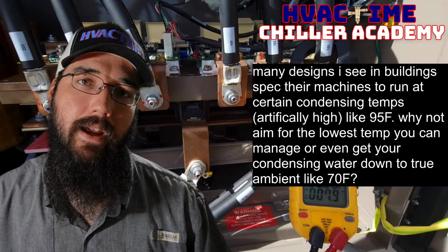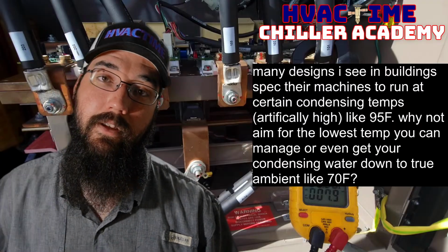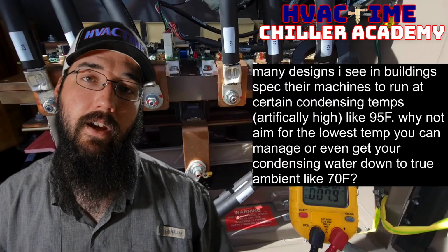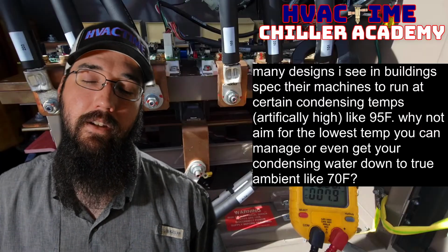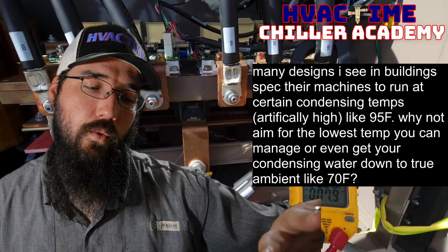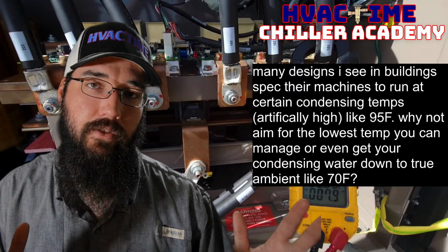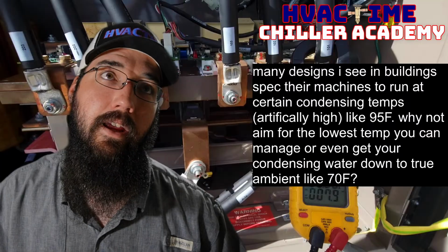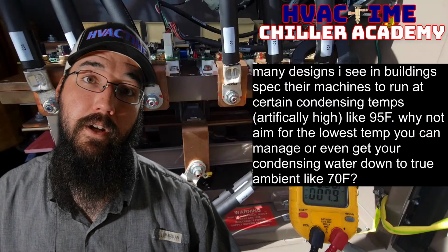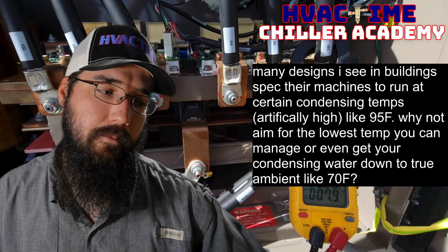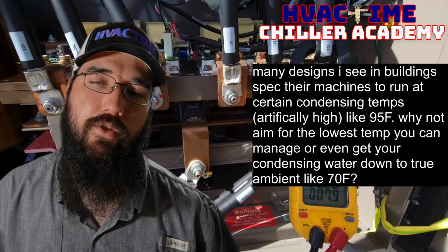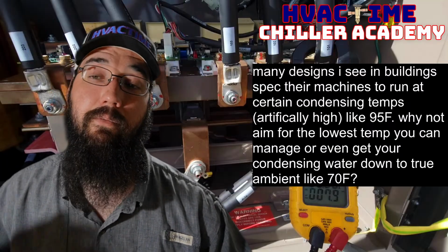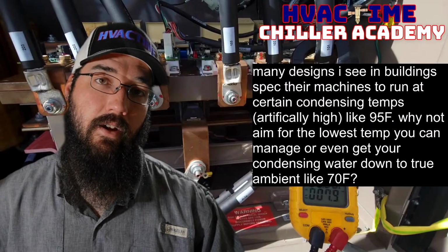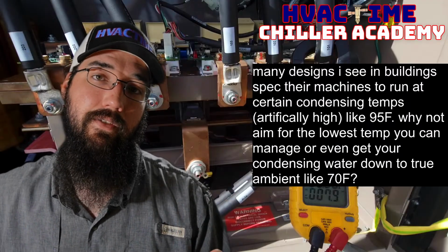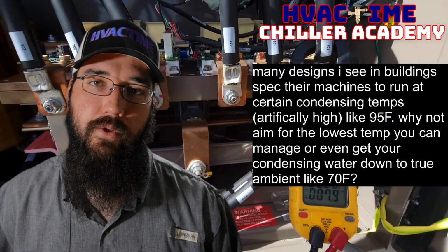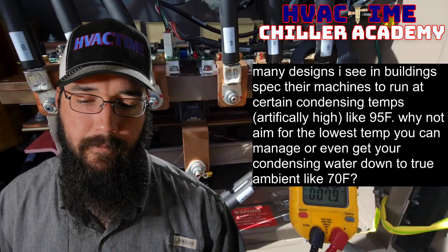Now, if I was dealing with a YK, those can operate at a much lower temperature, but they don't do quite as well at the higher temperatures most of the time, especially if I've got a site that doesn't typically load that chiller up all the way. So with a YK, I would use the same formula as to how we're calculating it, but I would set that lowest set point minimum to about 65. York says you can go as low as 60, but I prefer about 65, and I'll cap out at 80. So I'll let that one swing between 65 and 80 instead of the 75 and 85 to 90 with a Trane, as just two baseline examples here.